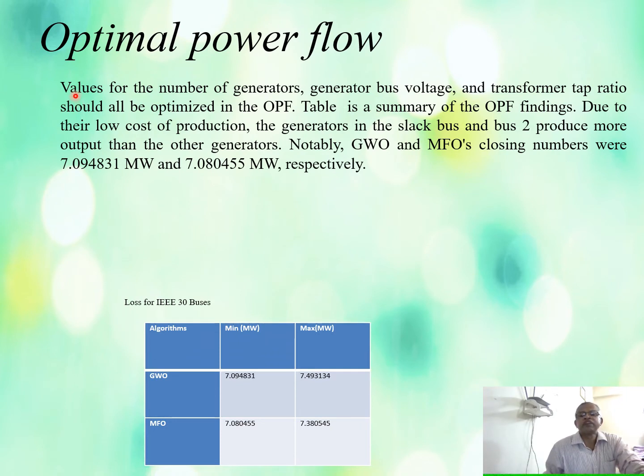Optimal power flow, that's the results. Values for the number of generators, generator bus voltage, and transformer tap ratio should all be optimized in the optimal power flow. Table 1 is the summary of the optimal power flow findings. Due to their low cost of production, the generators at the slack bus and bus 2 produce more output than the other generators. Notably, GWO and MFO closing numbers were 7.09 and 7.08 megawatt respectively.